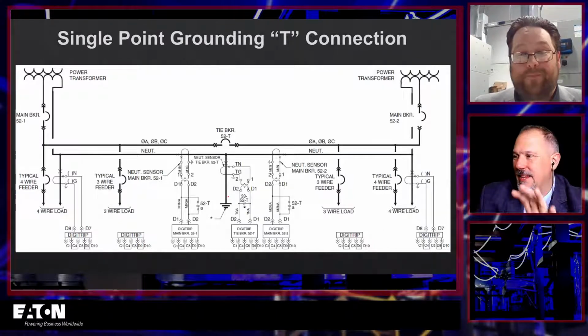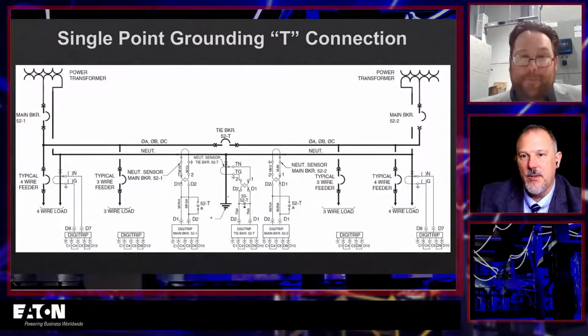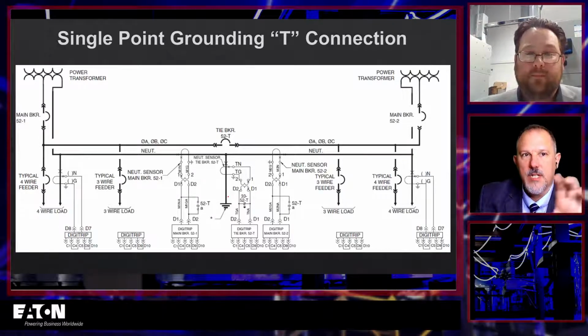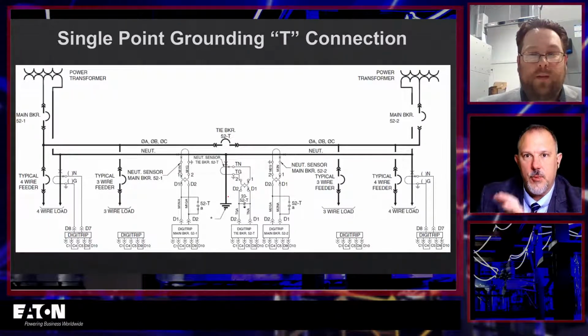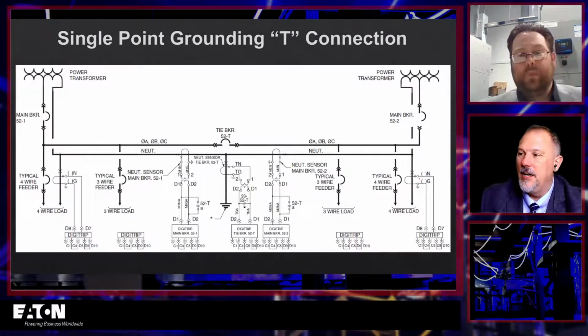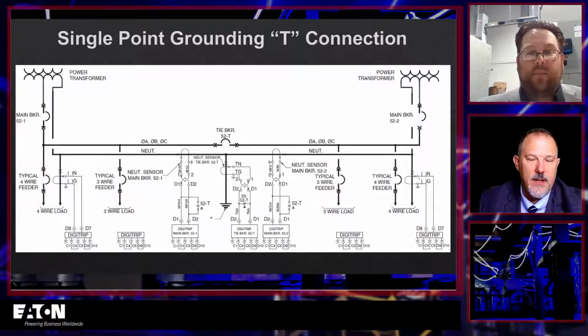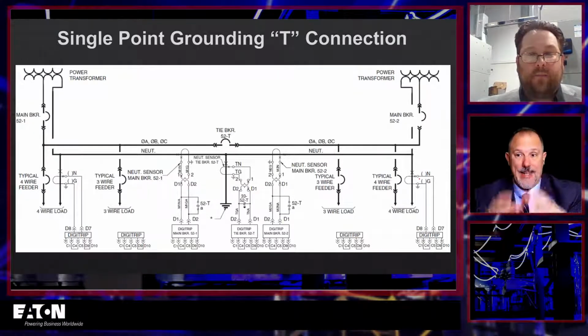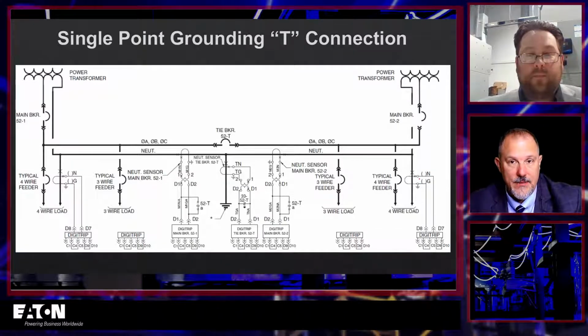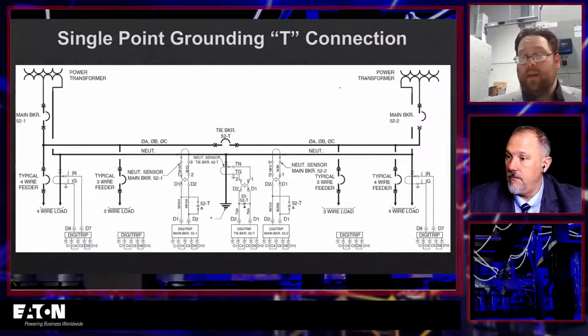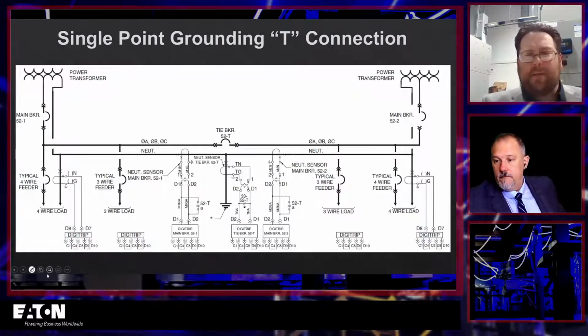That's exactly right. And I think that's a part of the challenge with all of this. You can go from a very simple single breaker installation, say a main in a panelboard, but when you start getting into the big stuff, the switchgear or switchboards, it gets much more complicated. And when you're dealing with double-ended switchgear and different types of bonding and grounding, and different types of, whether it's zero sequence or all of that good stuff that we just talked about earlier, it adds to the complexity. And so the qualified individual is really critical at that point. And then you're going to want to get the 240.87 and 240.67 done at the same time.